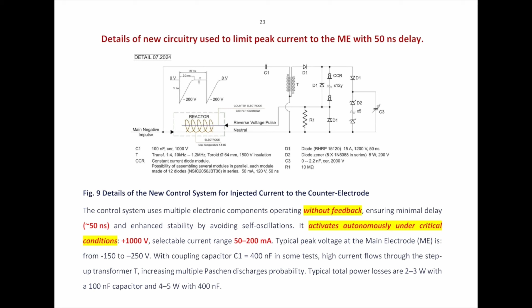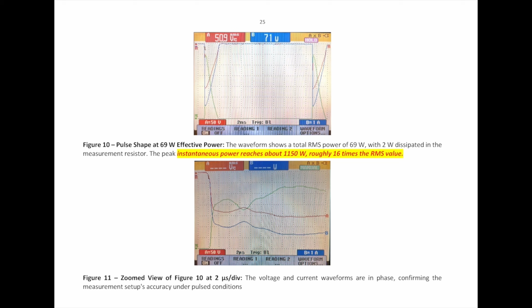Now I show you data. The first one is a typical pulse, at low power, now 71 watt. The pulse has a peak current in this experiment of about 6 ampere and voltage about 200. Repetition 50 Hertz, so 20 milliseconds. Here is detail about the phase of current and voltage. There is no delay, which means the data are reliable. And the green is the power applied. So the peak power in this region is about 1 kilowatt 200 watt, about 20 times larger than mean power. So again, in the line, strong power for a short time.